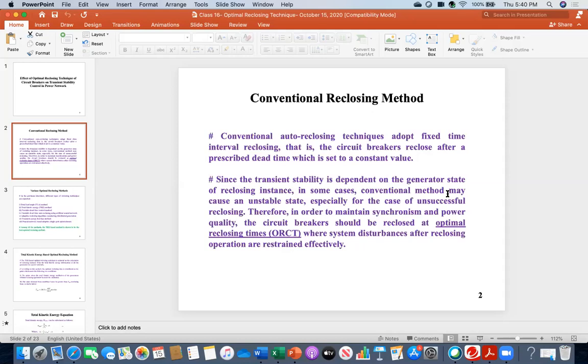Especially in those cases, the conventional method does not perform well, and the system might become unstable. That's why, to maintain system synchronism, power quality and transient stability, the circuit breaker should be reclosed at the optimal reclosing time. This is ORCT, the abbreviated form of optimal reclosing technique, where system disturbances after the reclosing operation are restrained effectively.